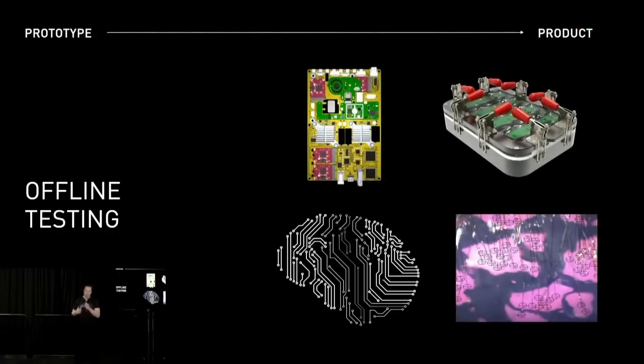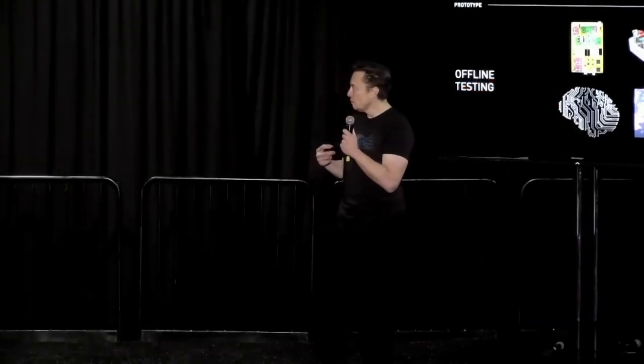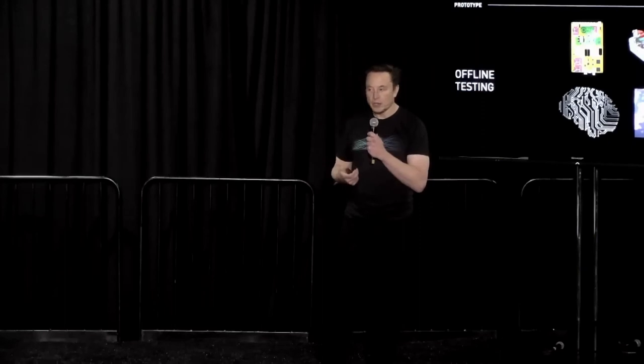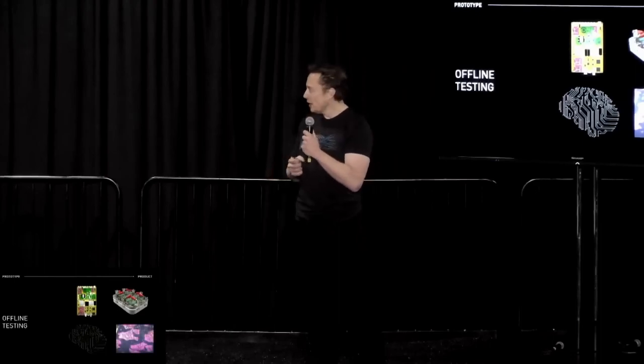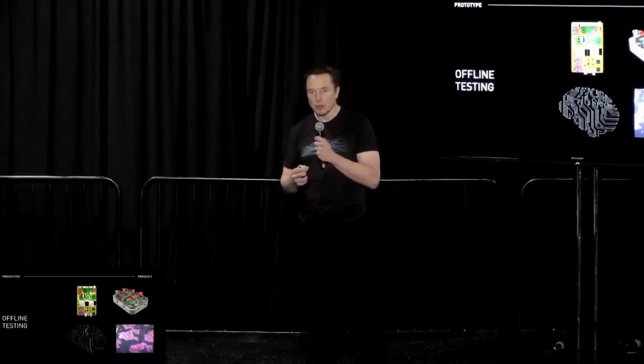So we do everything we possibly can to test the devices before not even going into a human, before even going into an animal. We do benchtop testing. We do accelerated life testing. We have a fake brain simulator that has the texture and is emulating a brain, but it's sort of rubber. We do everything we possibly can with rigorous benchtop testing. We're not cavalier in putting devices into animals.